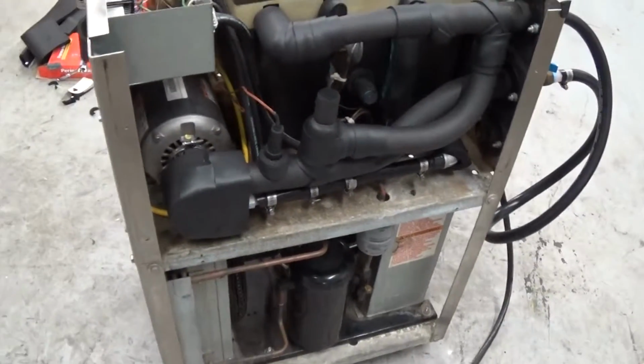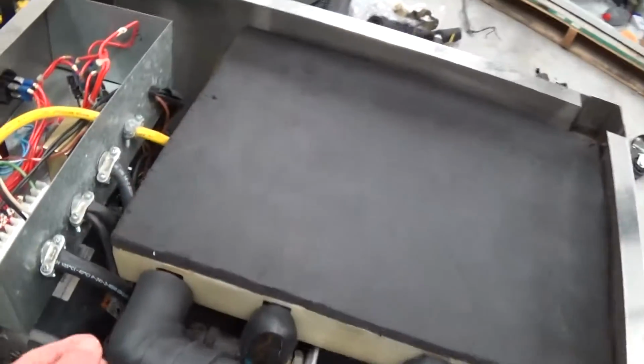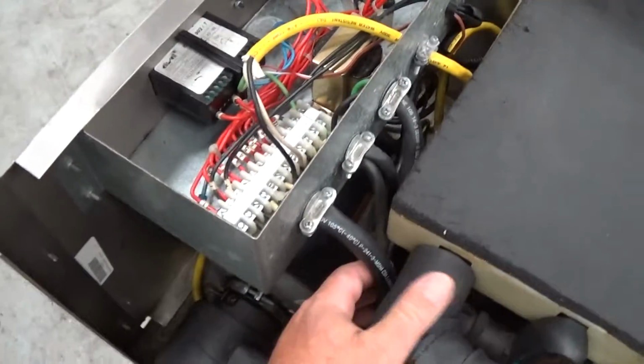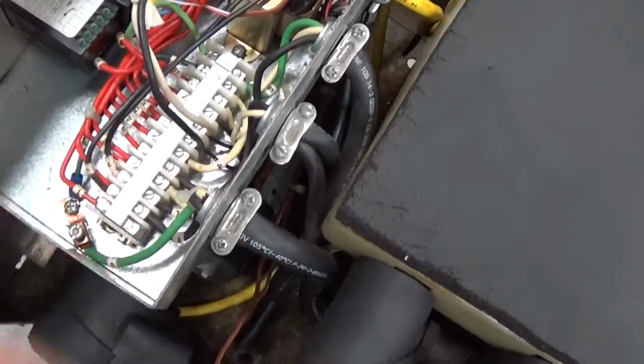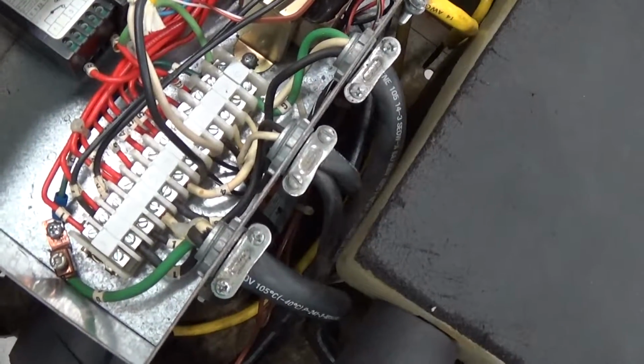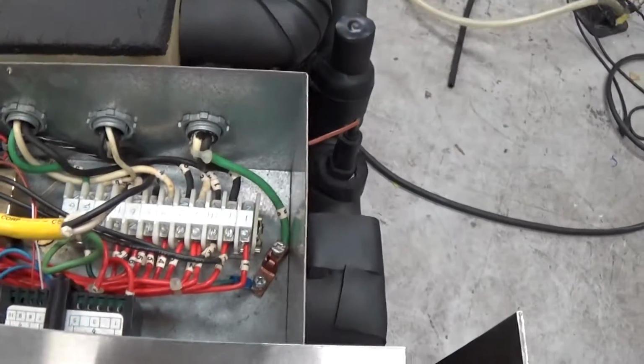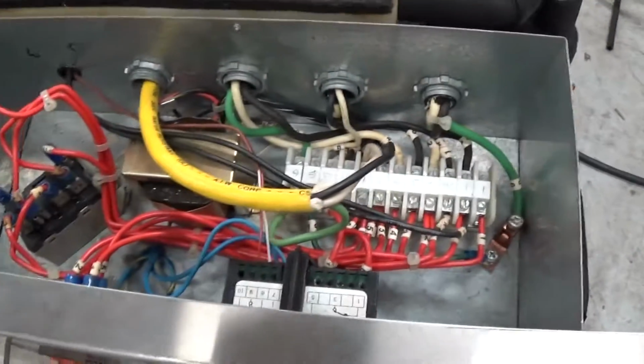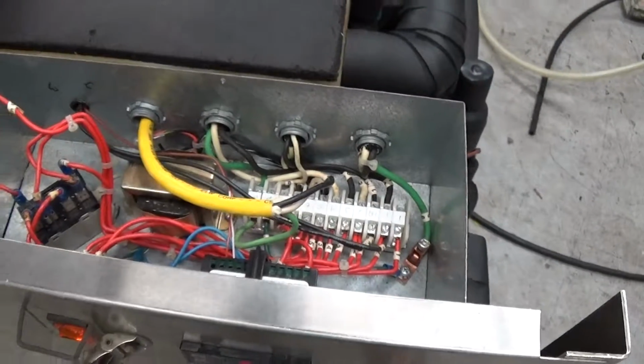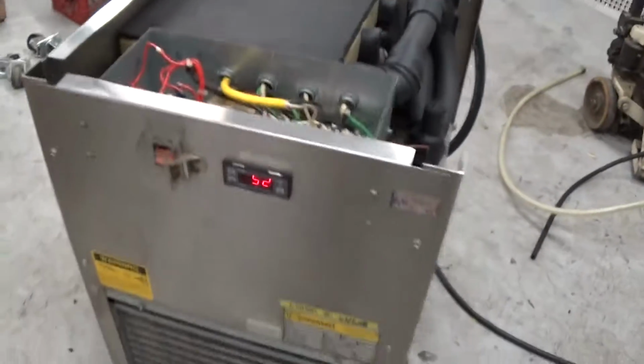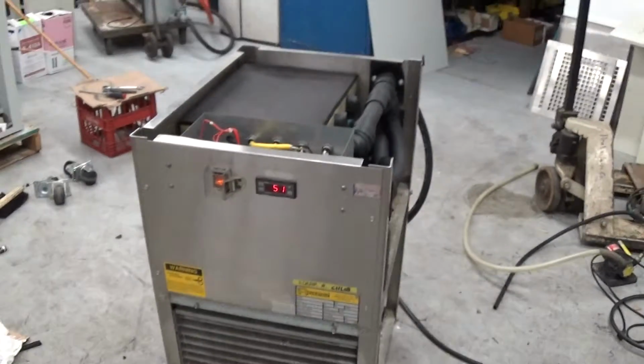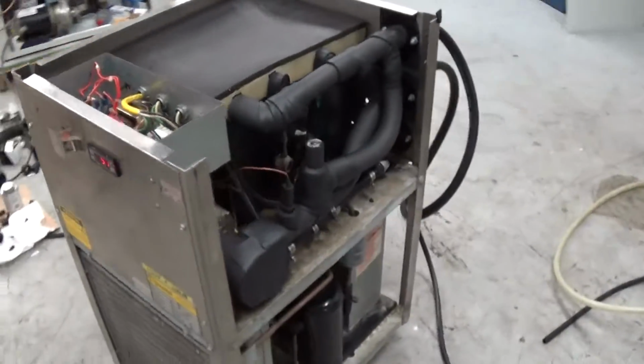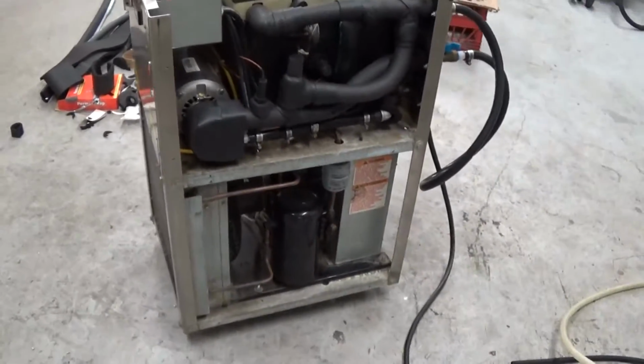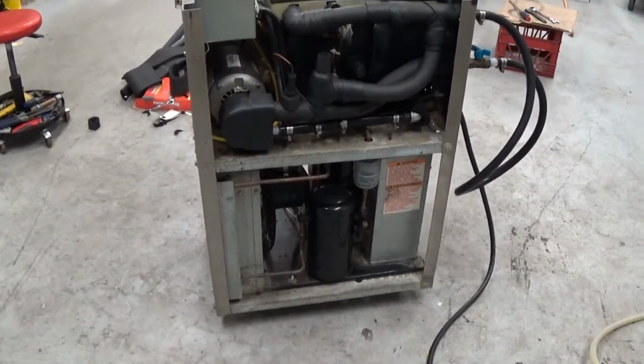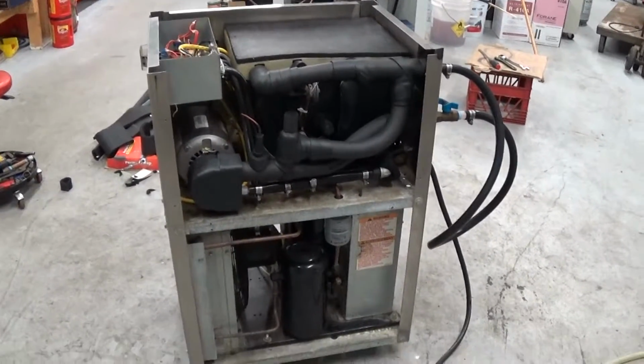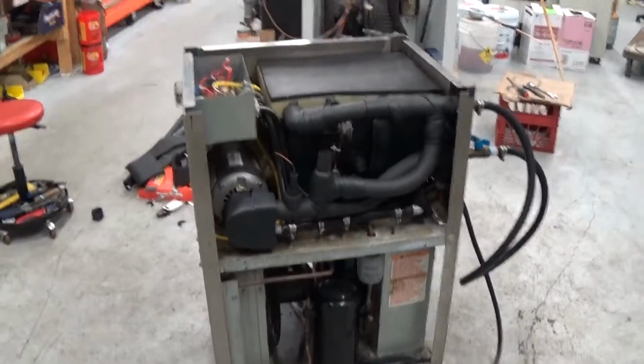than your typical braze plate heat exchanger. So typical, I'm pretty sure this will ship out with this SJO cord here, and that's just your single phase 208 power coming into the main here. We do have the full manual online for this actual chiller, and we leave it online, as well as the runoff videos for our customers to access. So we usually leave them marked sold, and we leave hundreds of chillers up online with the appropriate manuals, because we have about 30 different models that come through this shop.